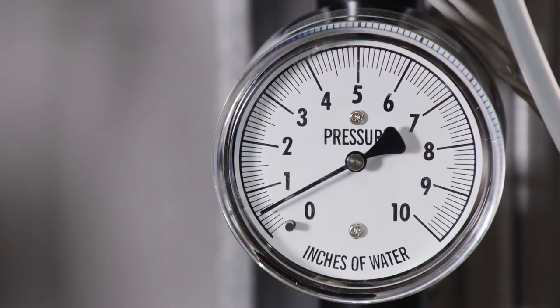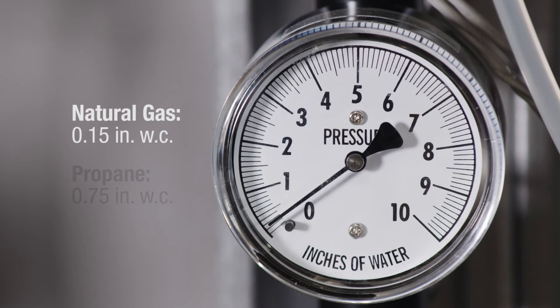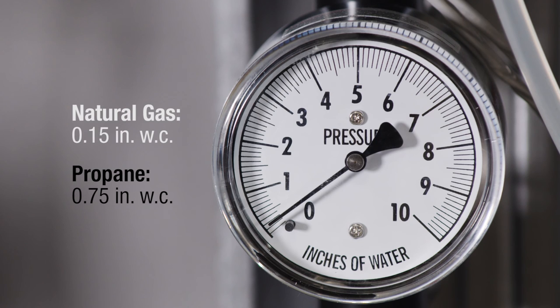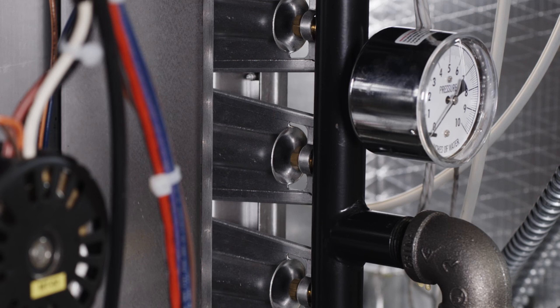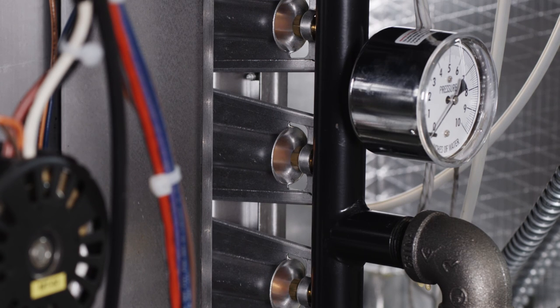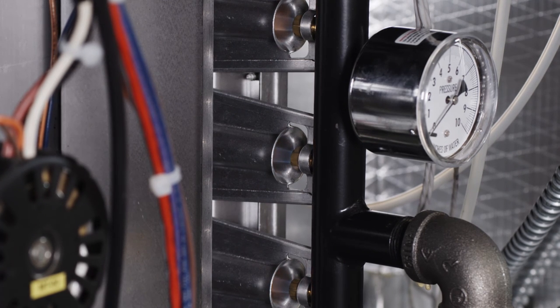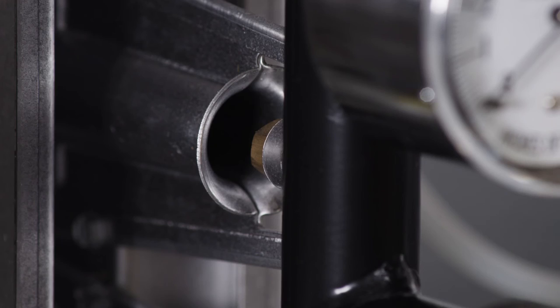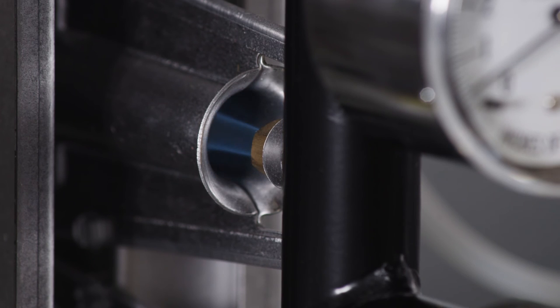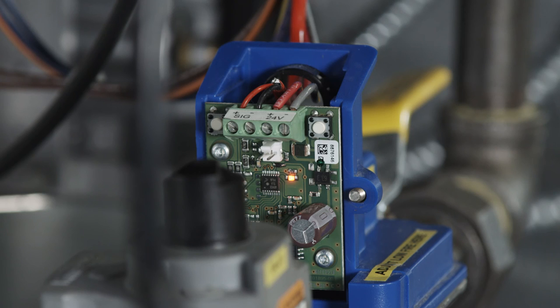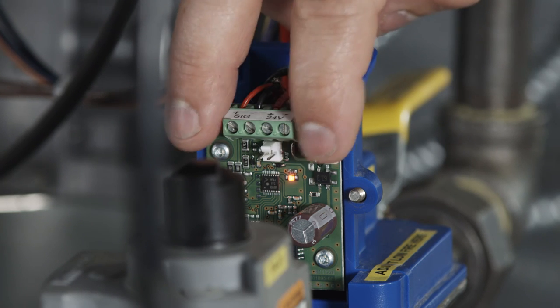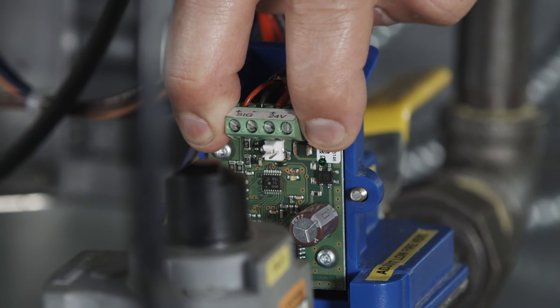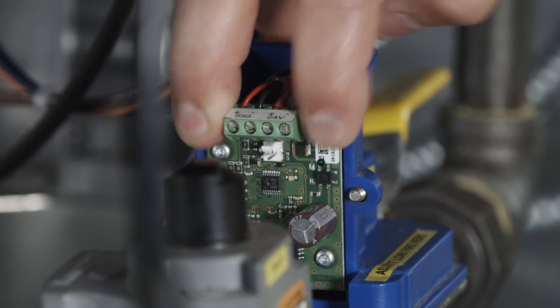While viewing the gauge, the pressure should be adjusted to equal 0.15 inches water column for natural gas and 0.75 inches water column for propane. If the low fire setting cannot be achieved due to flame dropping back into the orifice, set pressure as low as possible while maintaining a normal flame. Save the low fire setting by simultaneously holding down button 1 and 2 until the blinking LED light turns off.